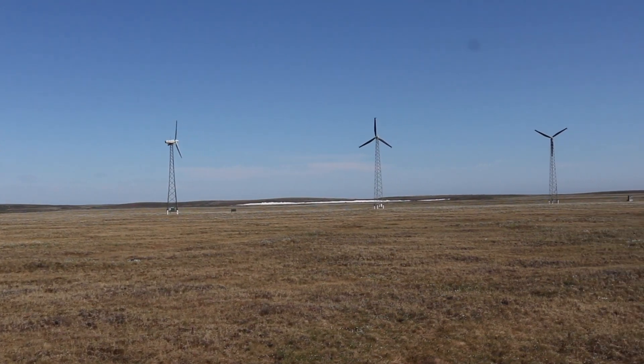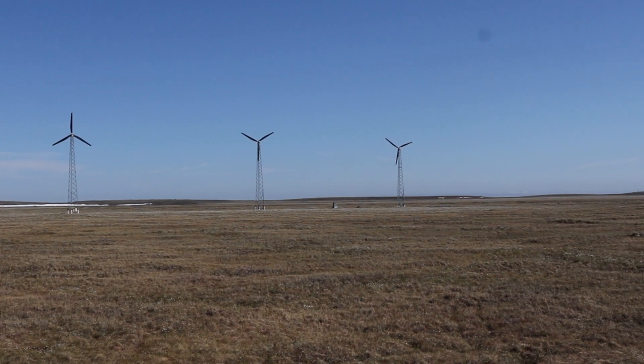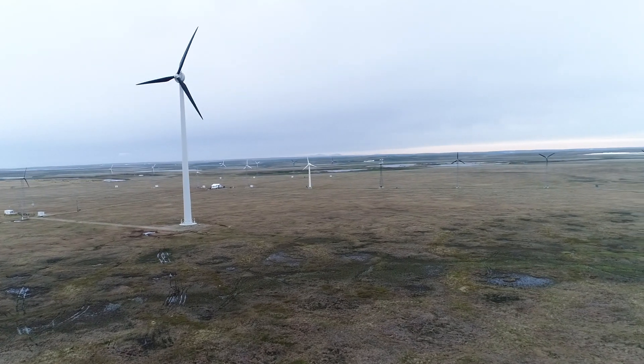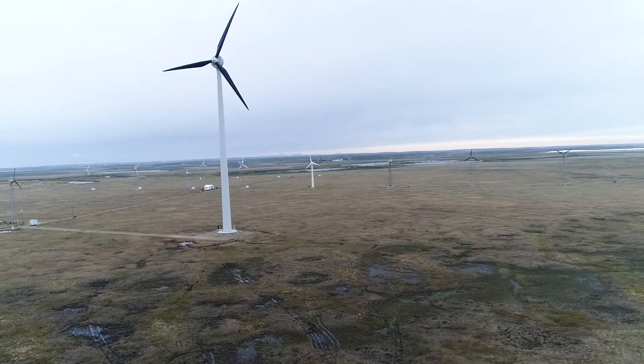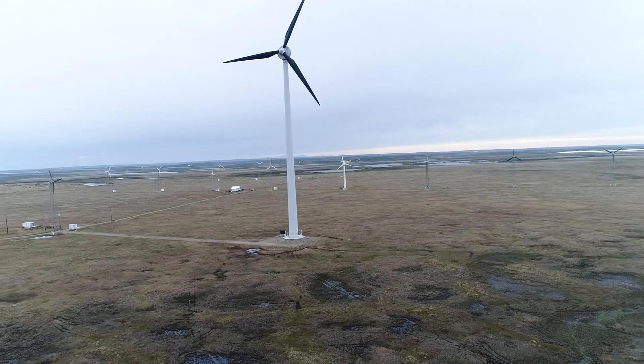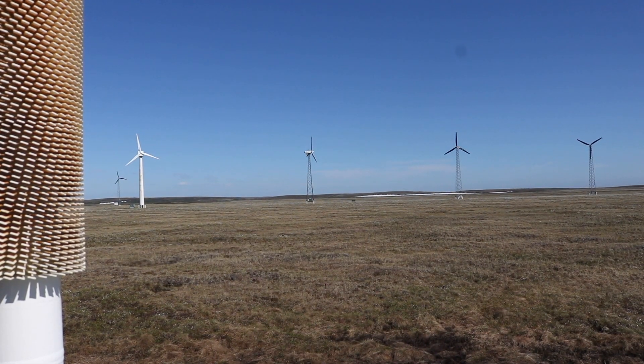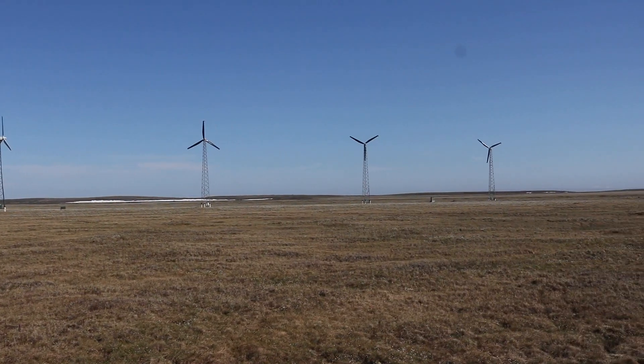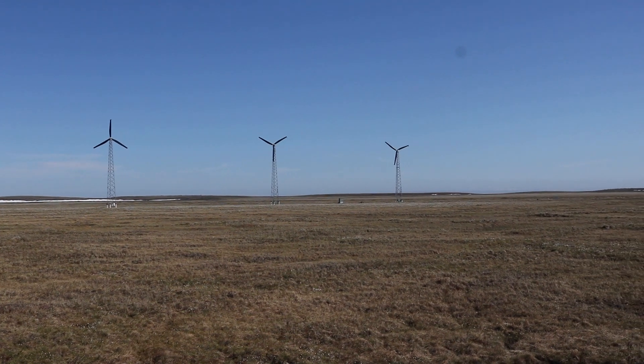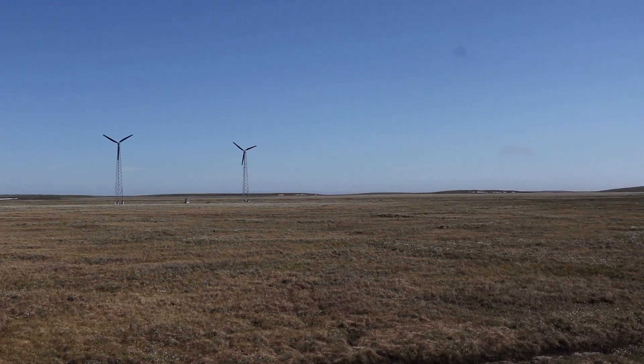Some of the biggest obstacles in wind energy in Kotzebue have been the permafrost on the Arctic tundra. All our machines are on permafrost — it's essentially like a low-grade concrete. If you can lock your wind turbine or structure into it and not melt it, you've got a pretty good footing to work on. We use devices called thermosiphons, which are essentially a device that removes heat from the ground. Shipping is a huge component of project cost, so a lattice tower is broken into smaller pieces and assembled on site, which made installation cost a lot less.